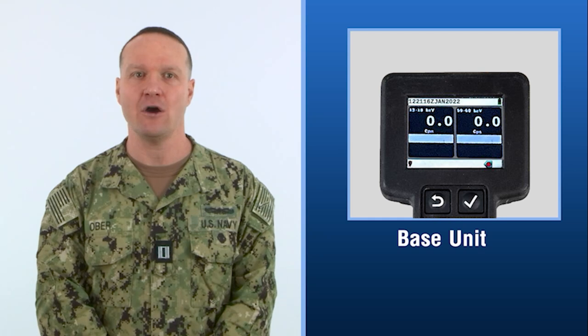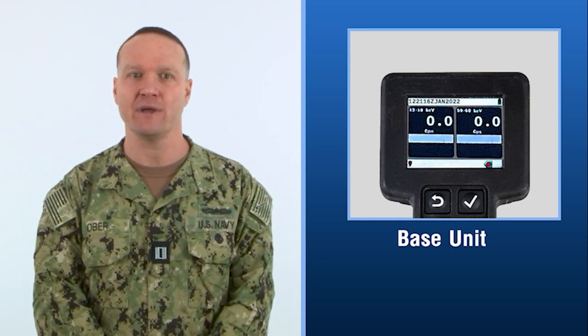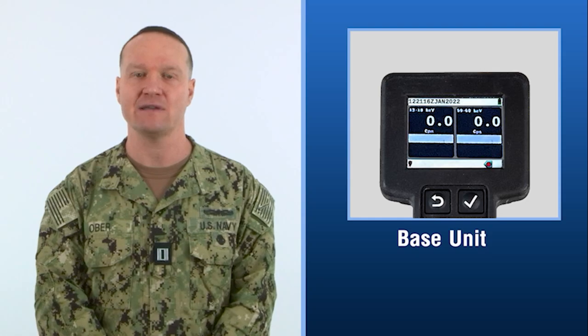The Fiddler probe detects and distinguishes between low-energy X-rays and gamma radiation. It simultaneously records data over 4 separate energy regions by use of a multi-channel discriminator. Analysis of this information can enable detection of materials commonly used in weapons of mass destruction. The Fiddler probe monitors 4 energy regions simultaneously. The base unit home screen has the ability to display 1 or 2 energy channels at a time.